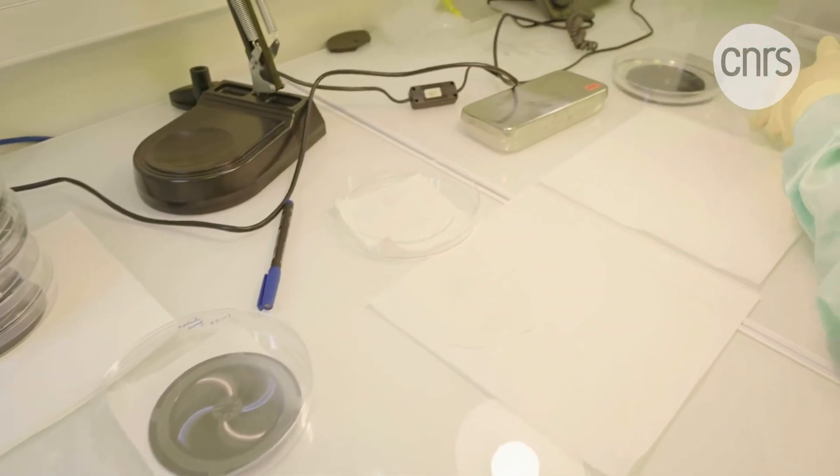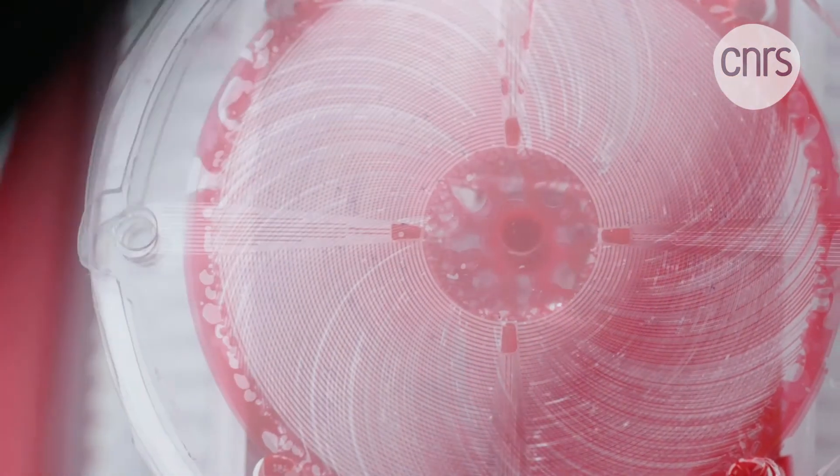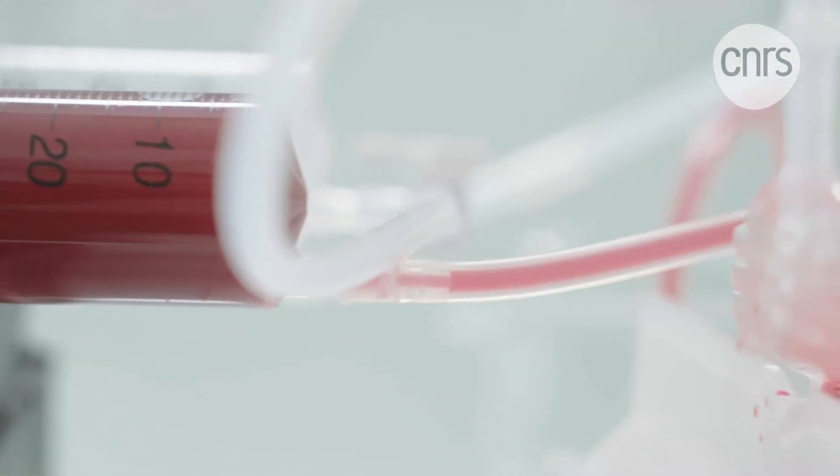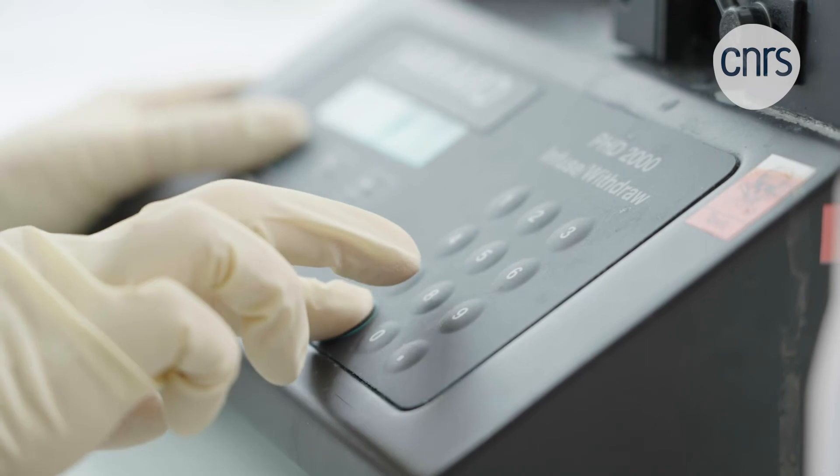Thanks to microfluidics and microfabrication techniques, we are able here to create devices composed of microchannels in which blood circulates, and microchannels in which oxygenation gas flows, whether air or pure oxygen. And between these two channels, a thin membrane allows the exchange of gas, transferring oxygen to the blood and releasing carbon dioxide. So this performs the physiological function of a lung. Here we can see that in three modules placed on top of one another, we have a blood circulation of 45 milliliters per minute.